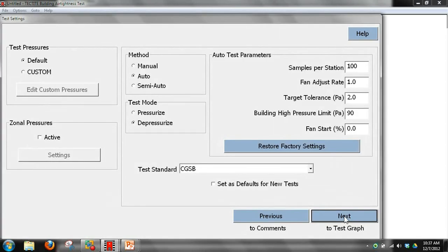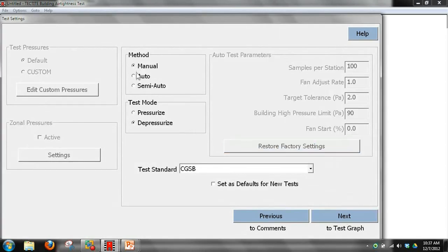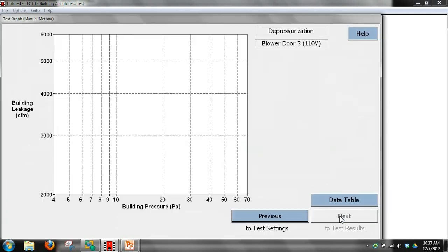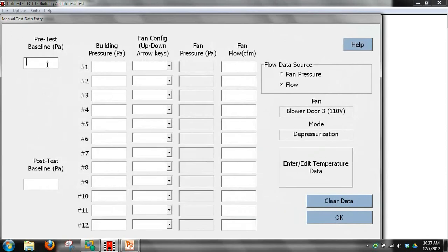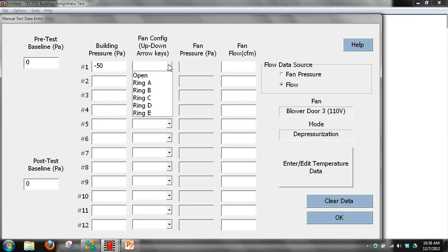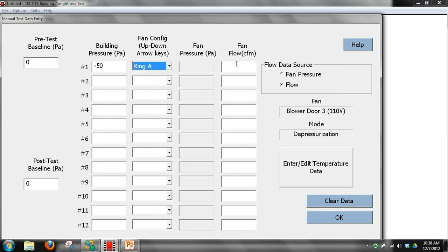We're going to do a manual entry. We can enter this information when we get back to the office or take it here. Because we used the baseline function of the gauge, we'll put zero in for the pretest and posttest baseline readings. Because we used the CFM at 50 function on the gauge, we'll put -50 in for our building pressure, ring A for our configuration, and 2,000 CFM for our fan flow.